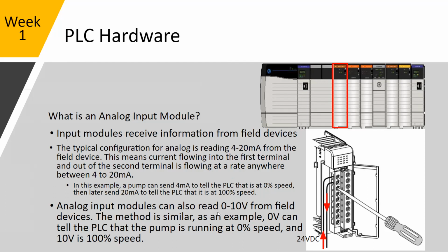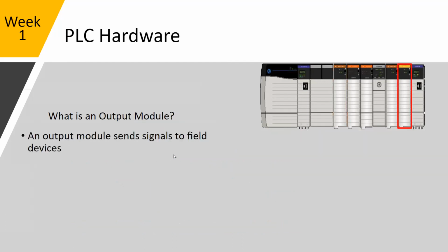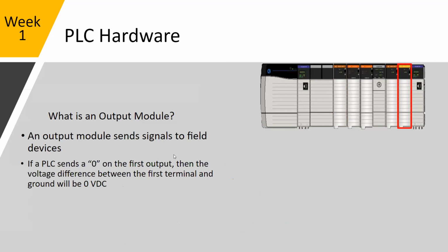Perfect. So the analog input is a good way to remember the inputs: you have some sort of variable device. If there's something that's going to be changing, whether it's a level, a flow, or a temperature, that's going to be an analog input. If you have something that either is or is not, it's in a fault state, it's open, it's not open, that's going to be digital. Output modules. These are very much the same.